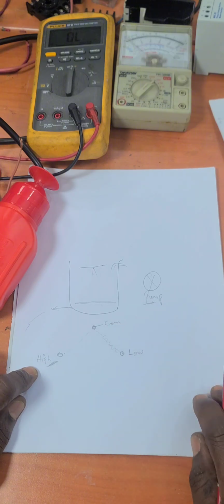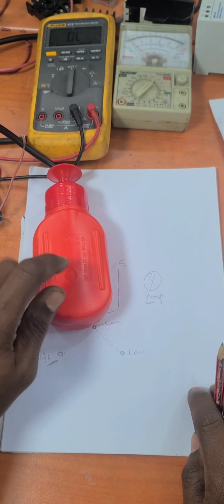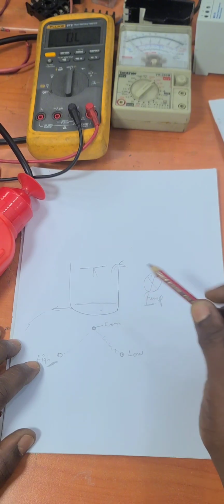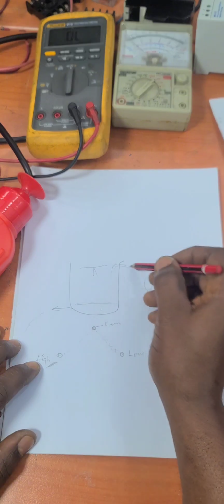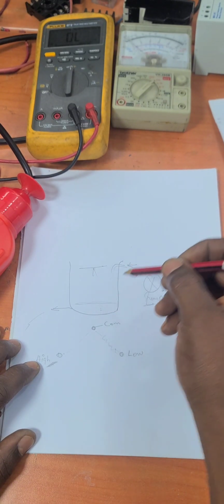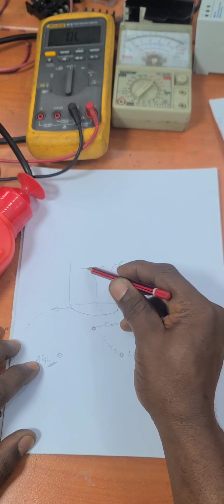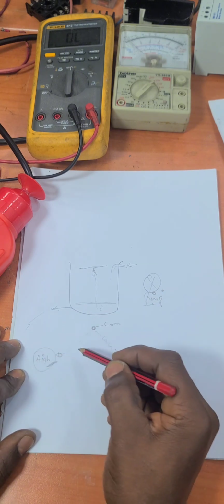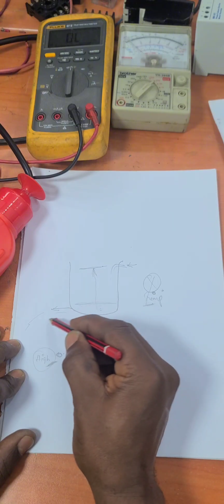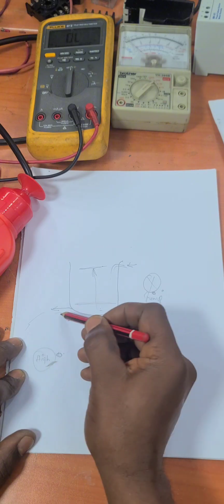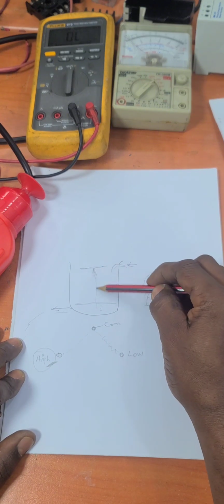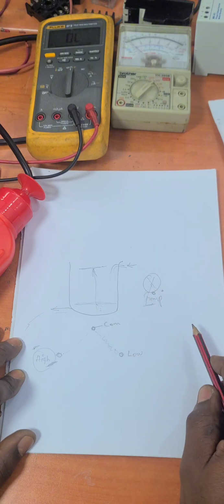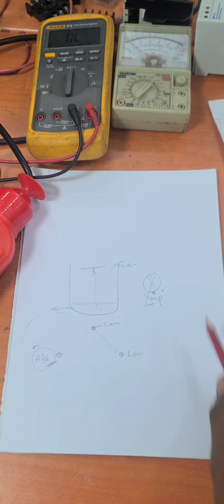So what we're going to do today is make use of this float switch to achieve a situation where when our water level gets low, it will activate this pump to pump water into the tank. And as water level rises up to this place, when it gets to this level, it will shut down this pump and activate another pump here, which will now pump water out from this pump to the users. And as it is pumping this water, when the water level drops again down to this place, it will disconnect this one and it will start this one again. So let us do the wiring.